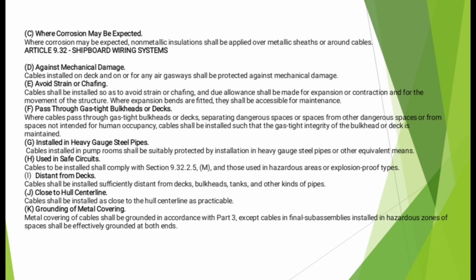Cables used in safe circuits shall comply with section 9.32.2.5, and those used in hazardous areas shall be of explosion-proof type. Distant from decks. Cable shall be installed sufficiently distant from decks, bulkheads, tanks, and other kinds of pipe. Close to the hull centerline. Cables shall be installed as close to the hull centerline as practicable.